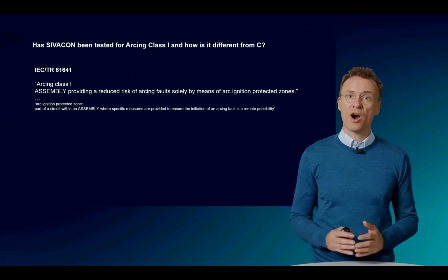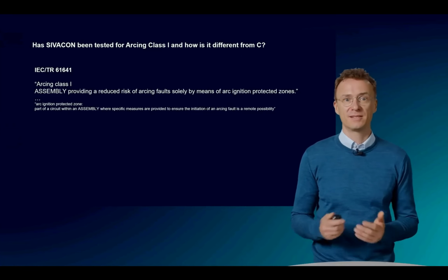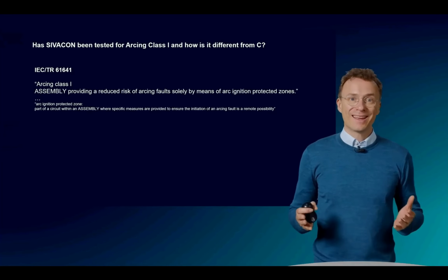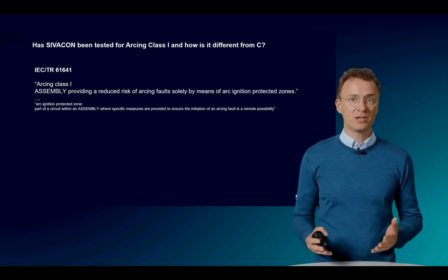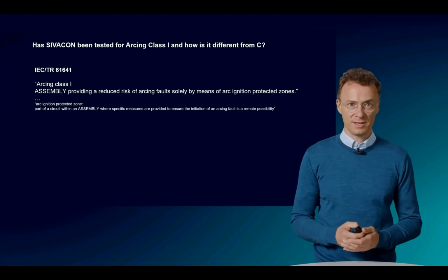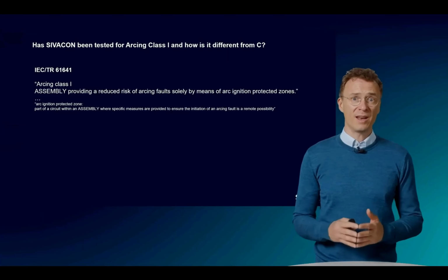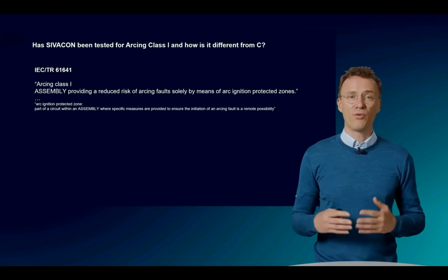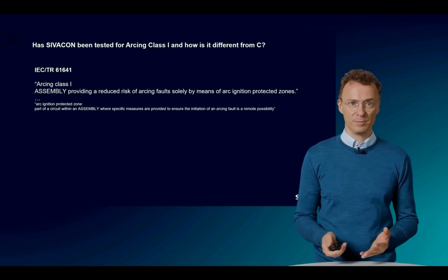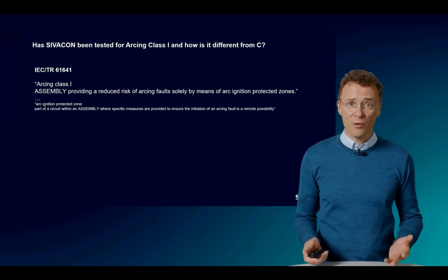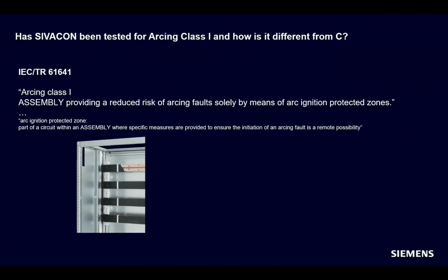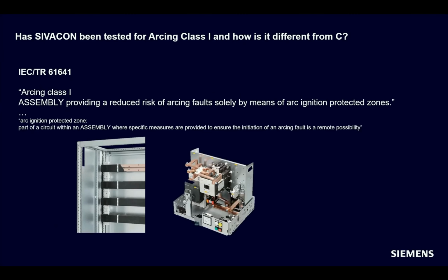Has Sivacon been tested for arcing class I, and how is that different from class C? Class I cannot be tested. Class I requires an assembly to be insulated so that no arc can be ignited. That insulation needs to provide an IP degree of protection IP4X so that no live parts are accessible. Parts of Sivacon S8 are realized in class I, however not the complete system. This is also a question of economy, as insulation requires significant additional effort. Sivacon S8 as a complete system is available up to class C, meaning that the design consists of tested and insulated zones.